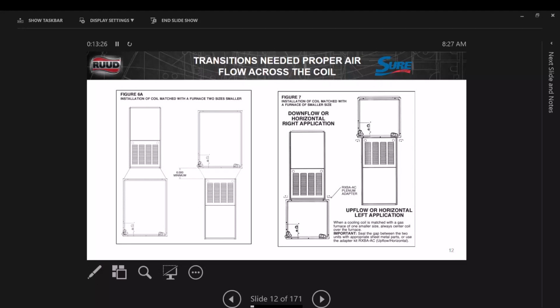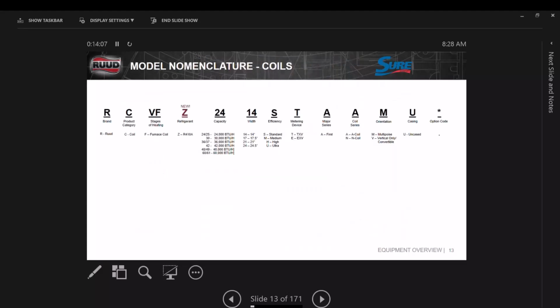It doesn't matter. But we're going to start stocking these. So they come in a box. You just snap them together. You can keep one on your truck. It's not big and bulky. So it's a transition to go from the furnace to the coil so that we have a perfect line. Plus, you have a place to take static pressure, because when you take static pressure on a gas system, you have to go in between the coil and the furnace, right, in order to get the whole reading.